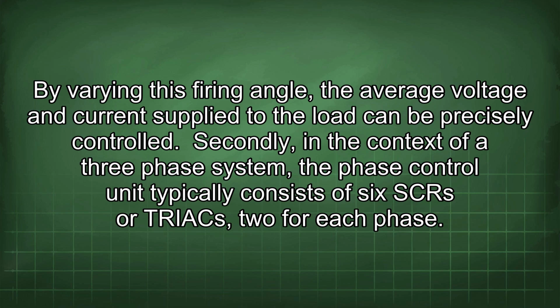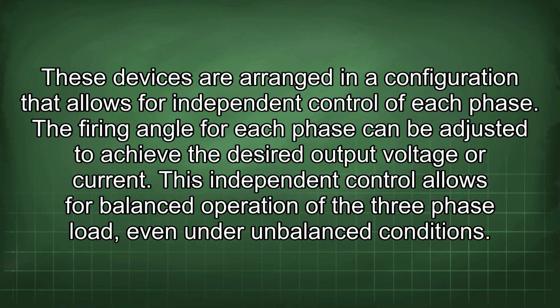Secondly, in the context of a three-phase system, the phase control unit typically consists of 6 SCR or triacs, 2 for each phase. These devices are arranged in a configuration that allows for independent control of each phase. The firing angle for each phase can be adjusted to achieve the desired output voltage or current. This independent control allows for balanced operation of the three-phase load, even under imbalanced conditions.